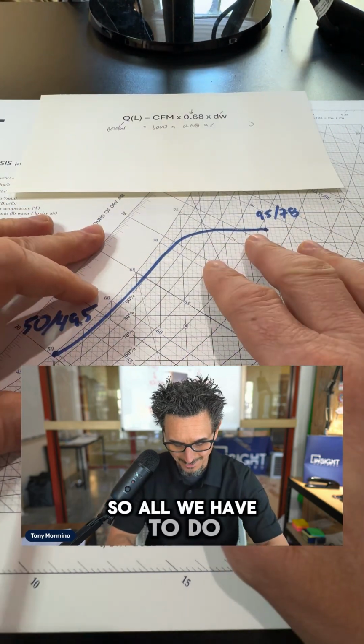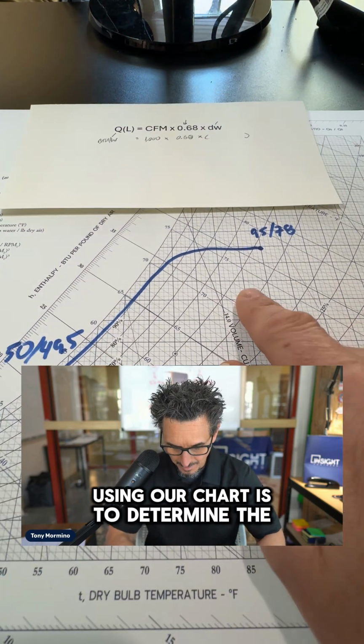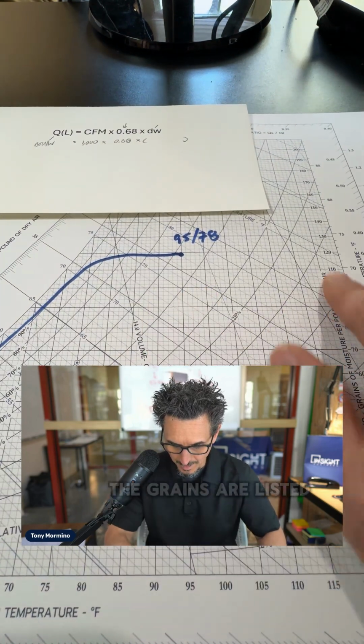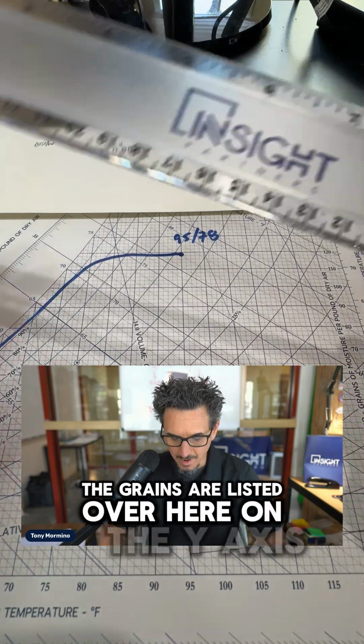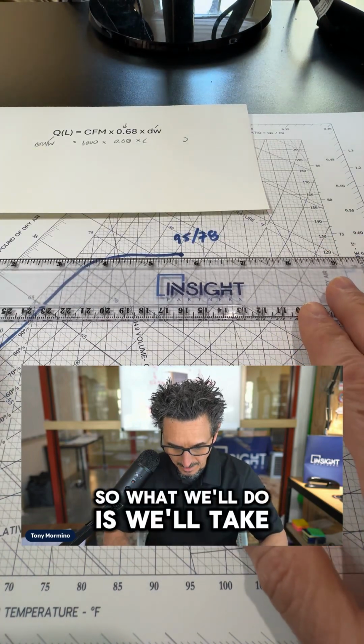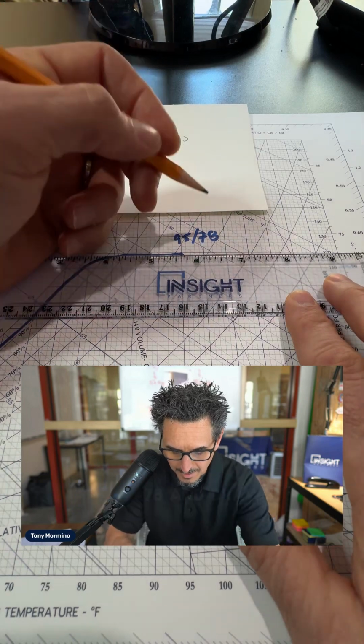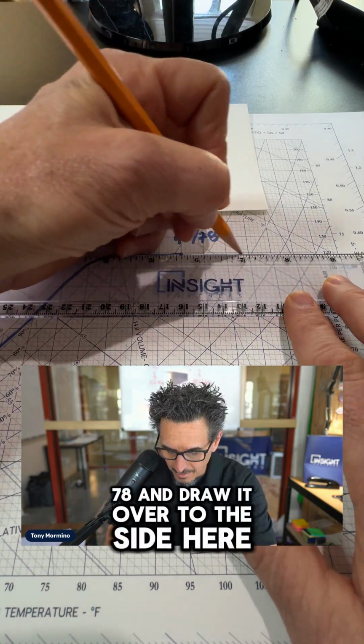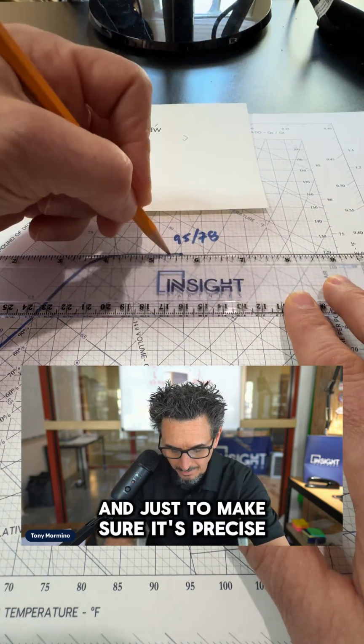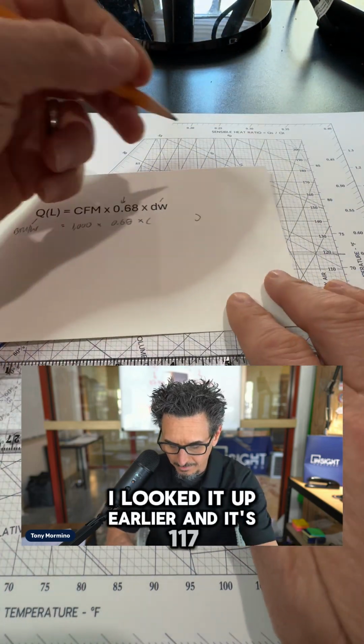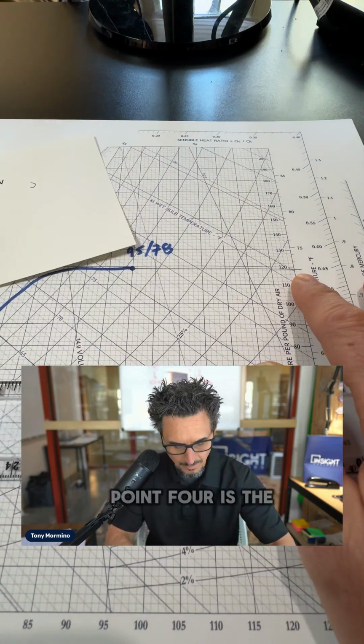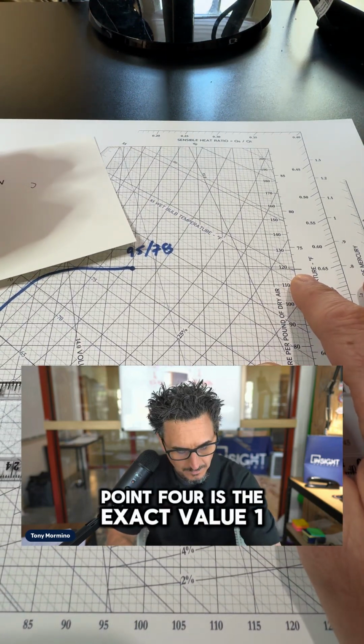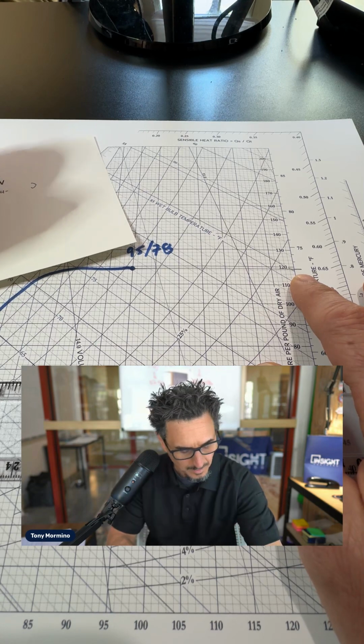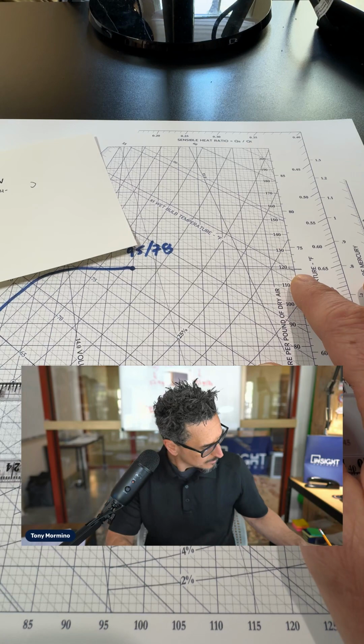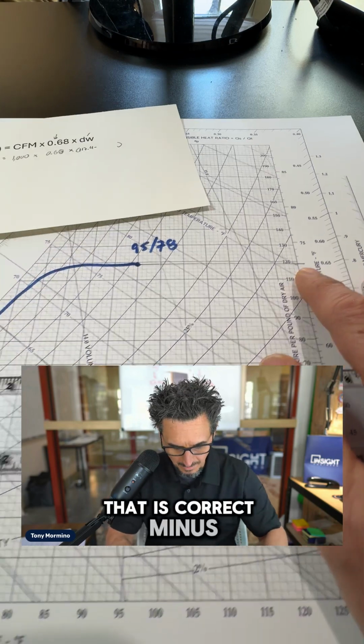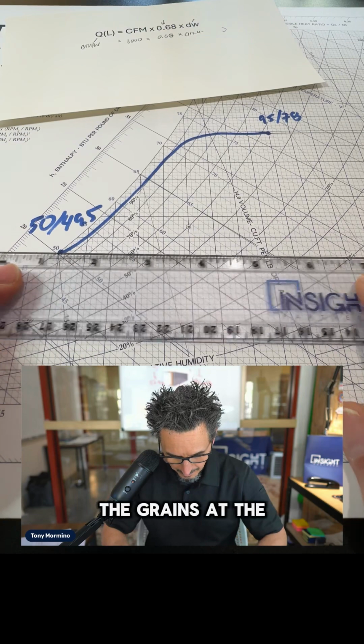So all we have to do using our chart is to determine the grains here. So how do we do this? Well, in this chart, the grains are listed over here on the y-axis. So what we'll do is we'll take our straight edge and we'll go from 95, 78 and draw it over to the side here. And just to make sure it's precise, I looked it up earlier and it's 117.4 is the exact value. Let me make sure I got that right. That is correct.